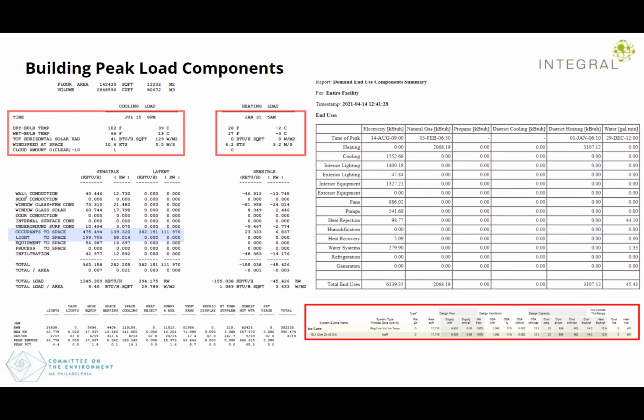Here, what I can see right away with the different, like you see wall, roof, conduction, you see window, glass conduction, solar, glass solar, you see occupants, lights, equipment, the different end users that contribute to your peak cooling load. And very quickly, I can see that the occupant and the lighting are really huge here. So my very first instinct at this point would be how are the occupants modeled? How many have they modeled? And is that realistic? For example, if this were a dining facility and I'm assuming all the 2,000 people are in this particular space at this particular time, is that justified? Are all the 2,000 occupants going to be in that space at that particular time? So just understanding that and reflecting on whether the inputs make sense is a very important part of analysis.